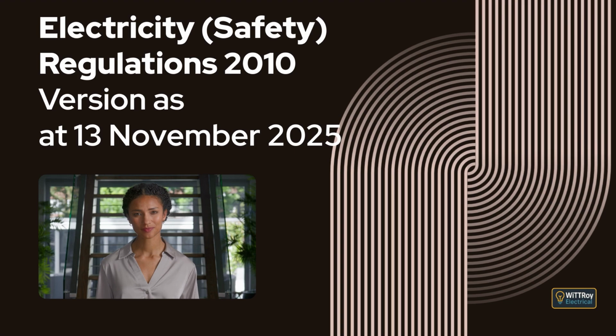It explains that if WorkSafe charges a fee to supply warrant forms, that fee must match the amount set out in Schedule 5. The regulation finishes by explaining that a person commits an offence and is liable to a Level 1 penalty if they issue a warrant otherwise than in accordance with this regulation, issue a warrant for a connectable installation that is electrically unsafe, or issue a warrant without being authorized to do so.